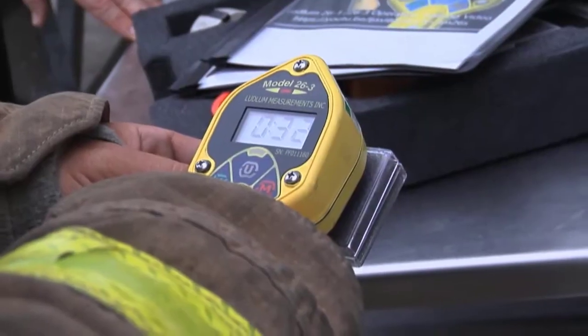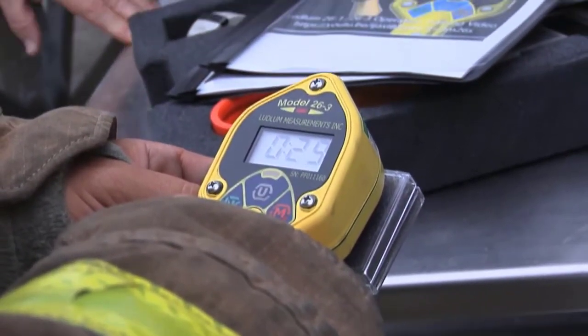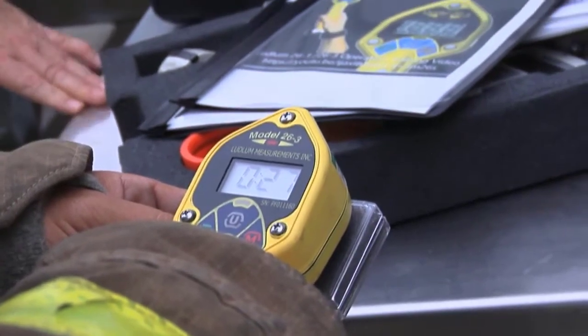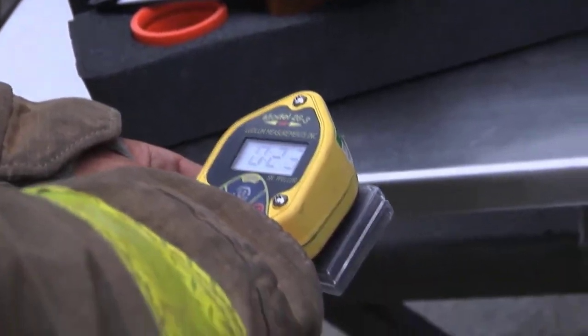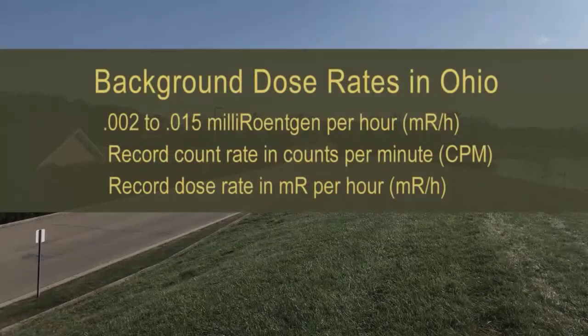At a safe distance from the scene, perform an operational check of the Model 26-3 and take background measurements. The background measurements should be taken away from any radiation sources. Background dose rates in Ohio range from 0.002 to 0.015 milliRoentgens per hour, or mR per hour. Record the background count rate in counts per minute, or CPM, and the dose rate in mR per hour.